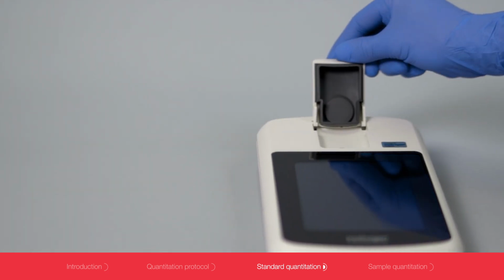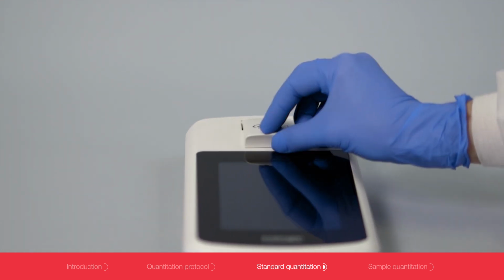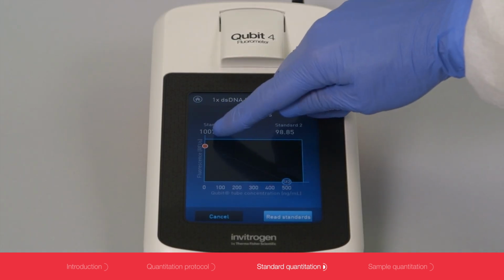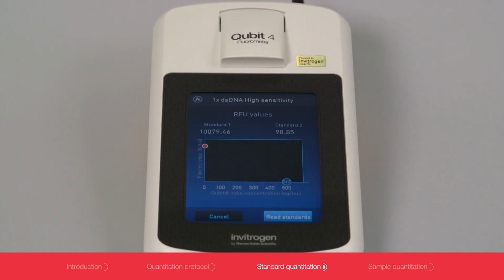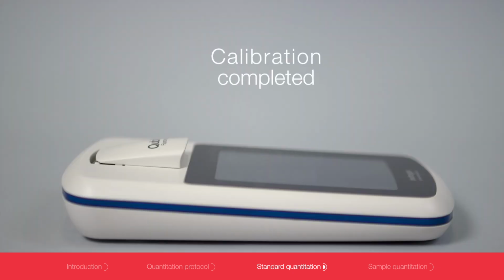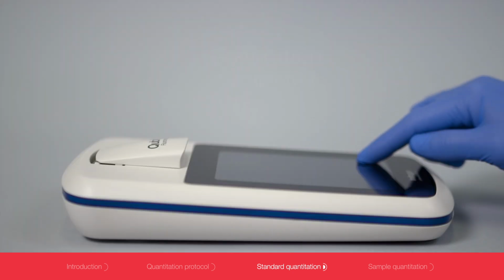For example, if you were to accidentally put Standard 2 in first or in place of Standard 1, both values and the graphical display will reflect this error. When the calibration is complete, you can run your samples.